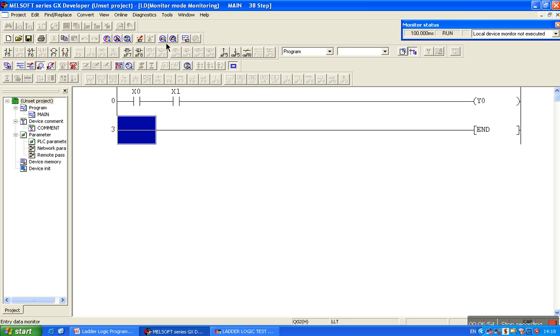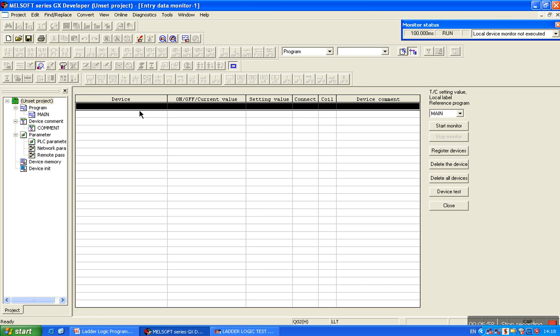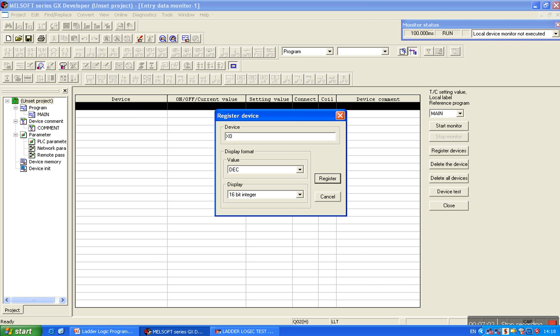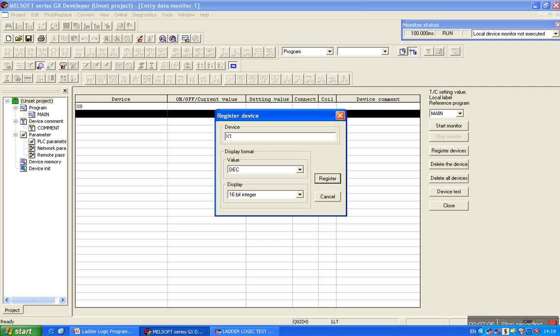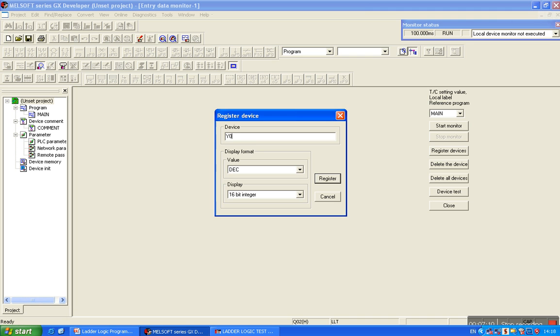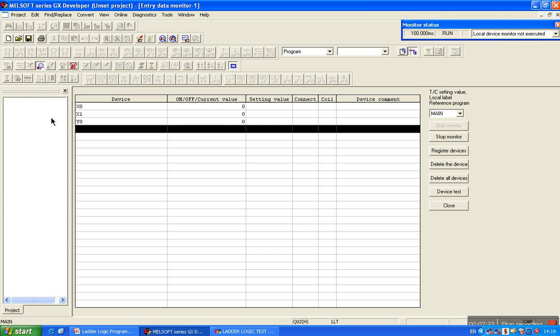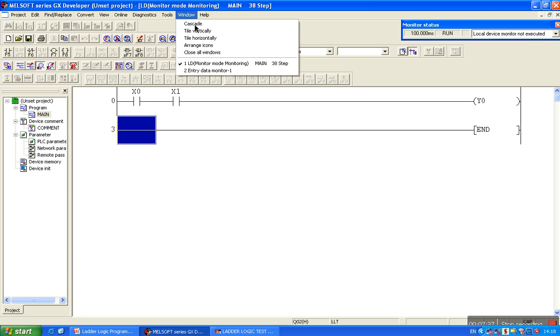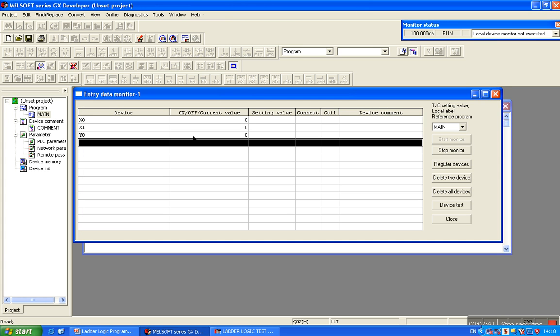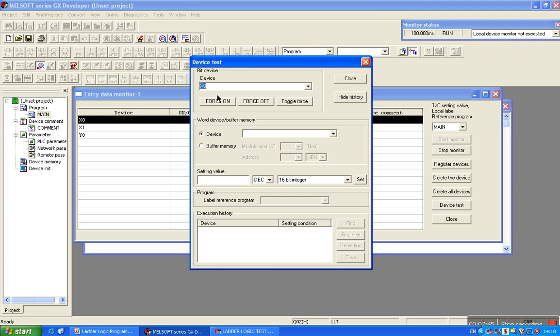Now click on Entry Data Monitor. Select device X0, the register, then X1, and Y0 as the output. Now change the value or restart the monitor. Here X0 and X1 are both 0 since no input has been applied. You can click on the window and select Cascade to see both the data monitor and main program. In the data monitor, you can set values.